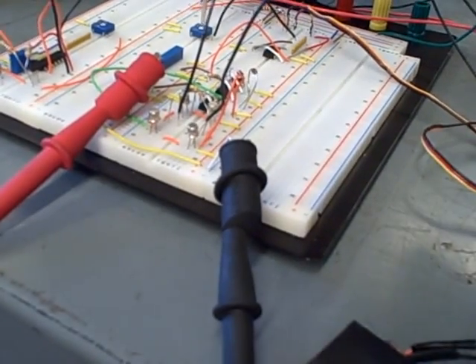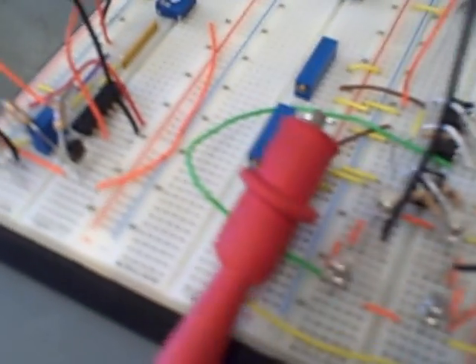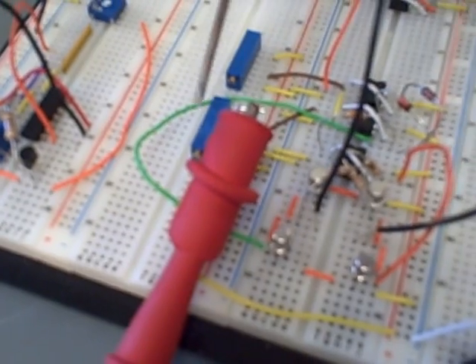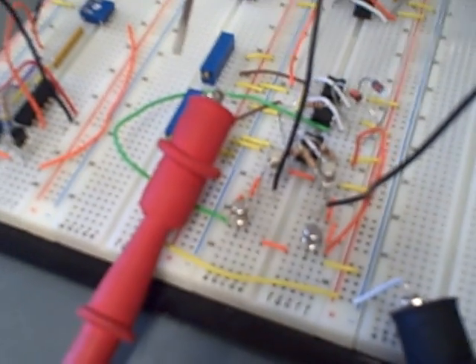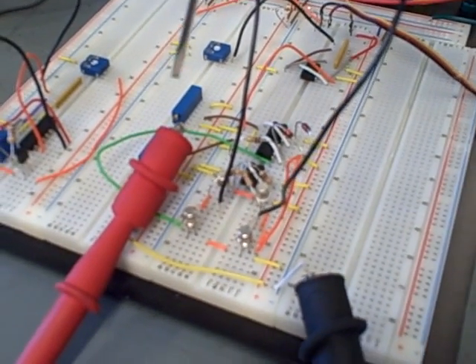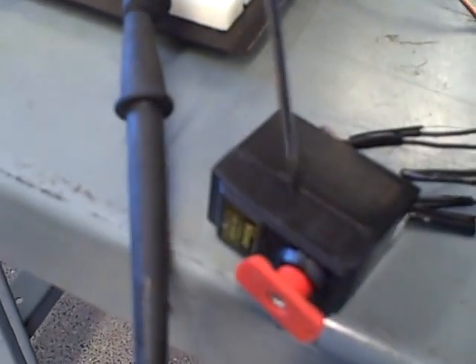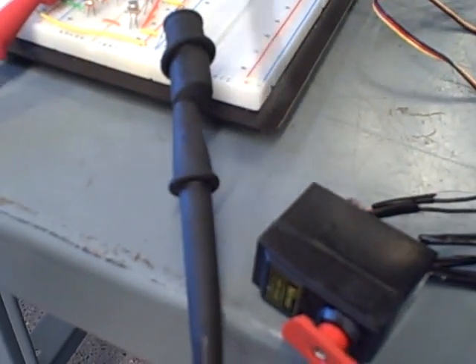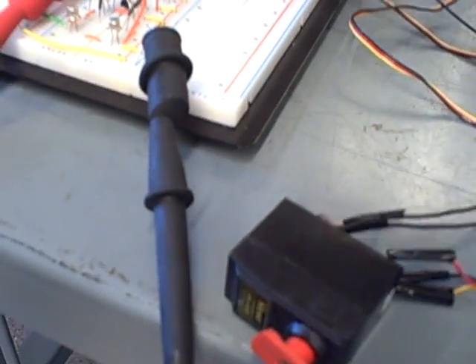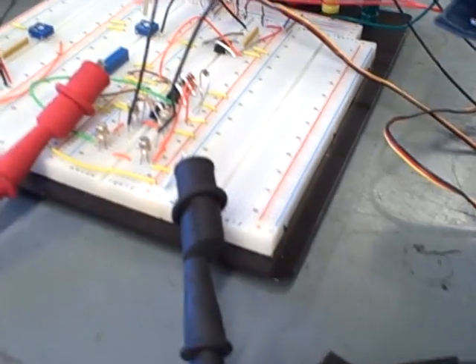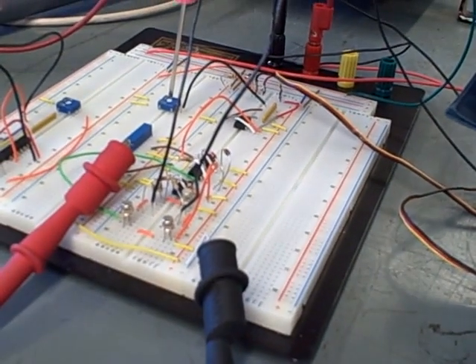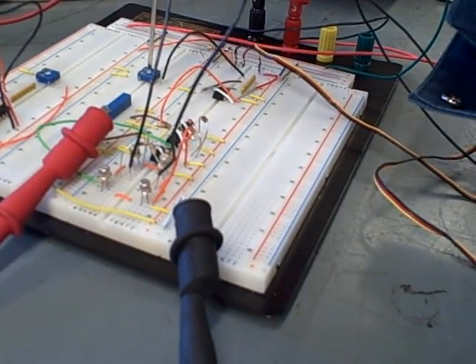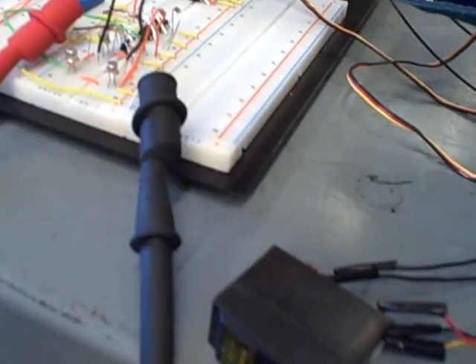What we've done here is we've been doing some experimentation with some of the other potentiometers in the circuit. These two potentiometers set the window voltages, or the limits, for driving the servo when it gets out of bounds or away from setpoint too far. We've tightened that up, so right now we have a total deadband of only 0.1 volts out of a 4 volt span, 1 to 5 volts over here. That's about a 2.5% deadband.